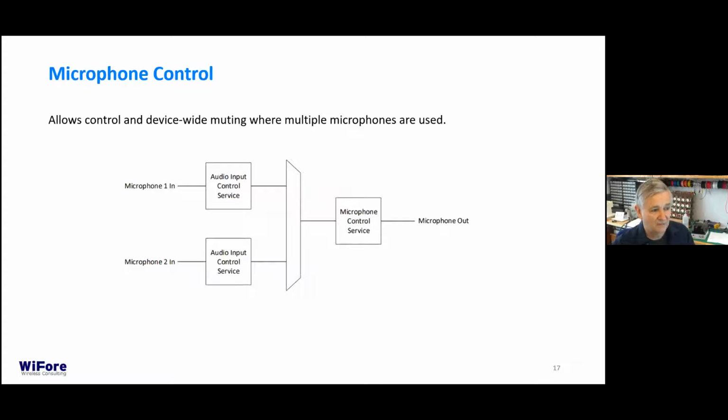Same if you've got microphones and you've got multiple microphones coming in, we can coordinate the time at which you capture everything. We coordinate the time at which you play everything as well. So if we're sending left and right signals to your hearing aids, we can actually set the time that they play and render to within a few microseconds, not milliseconds, actually down at the microsecond level. And that means you don't get any jitter or a feeling that the sound image is moving around in your head.